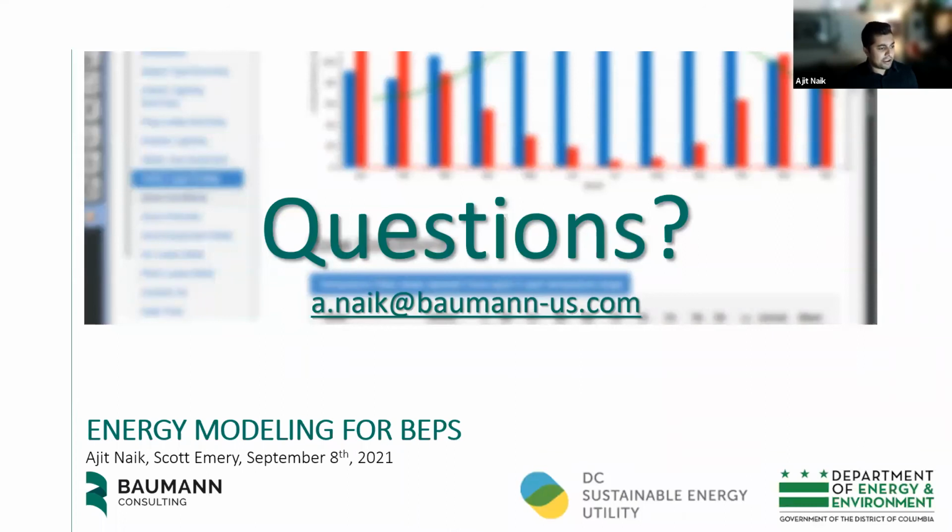Scott, I know there are also some pathways for reducing your site EUI, so I'm not sure this would help in that framework. Can you comment on that? Yeah, sure. I did want to make that point. If you're non-compliant currently, then the requirement is a 20% reduction of site EUI. And certainly converting, say, a fossil fuel-based heating system to a heat pump system will reduce your site energy. It's a very efficient technology, but you do have to pay attention to that balance between your site energy and your source energy. The tricky part is you could get that 20% site energy reduction, but if you don't have a really high efficiency heat pump solution, you may actually increase your source energy, which would decrease your Energy Star score.